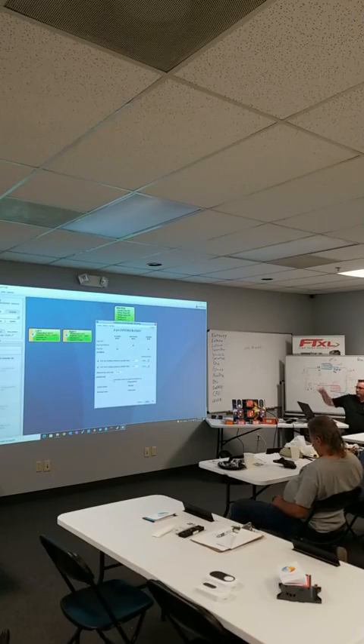Maybe on an M2000, which is what I have here, you want to use digital output 5 to do a powered exhaust. Maybe you want to do it on occupancy. Maybe you want to do powered exhaust based on your economizer position. So you could start the digital output based on what the economizer output is so that it will start a fan. Same thing with using differential in this scenario: at 45% open, power exhaust is going to start; at 25, power exhaust is going to shut off.